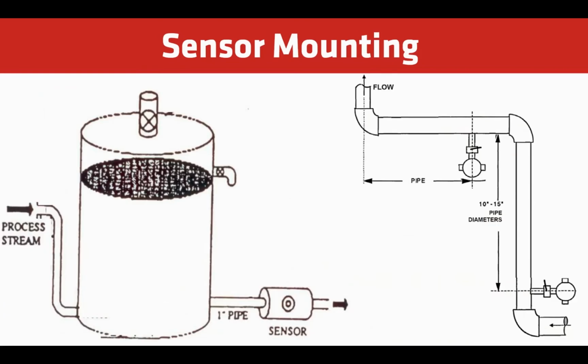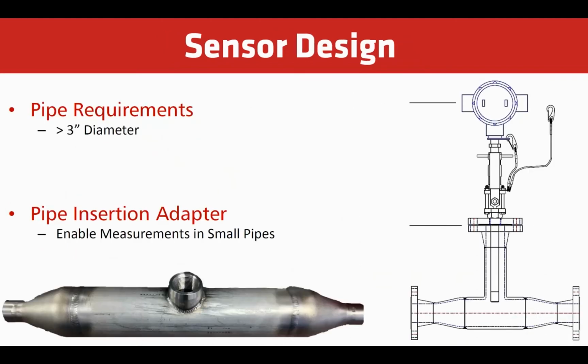or in piping, again, it's showing the importance of at least 10 to 15 pipe diameters away from any elbows. We need at least 3-inch diameter because it's very hard to mount on smaller piping, since the far wall is going to be too close to the sensor tip, and that will interfere with the readings. So again, a minimum of 3-inch diameter piping. If you do not have 3-inch diameter piping, we can offer one of these 3-inch to say 1-inch or 2-inch flow cells where the analyzer can be mounted.